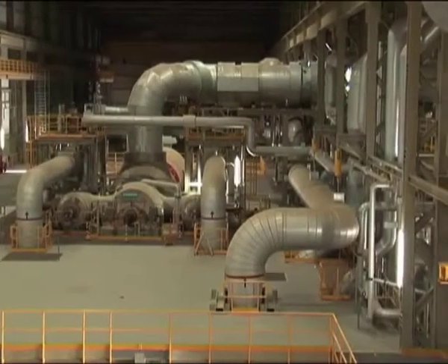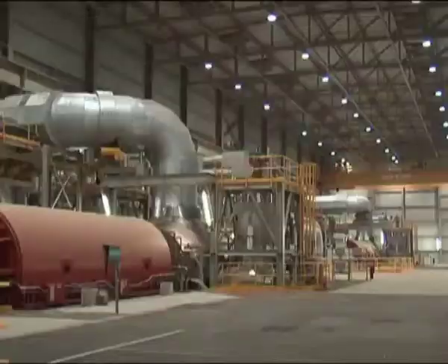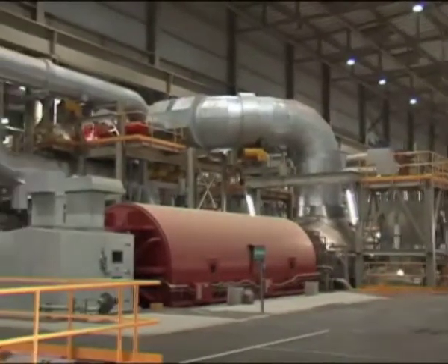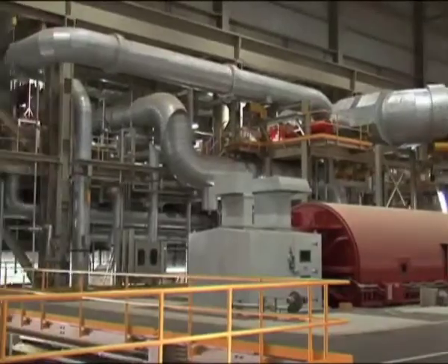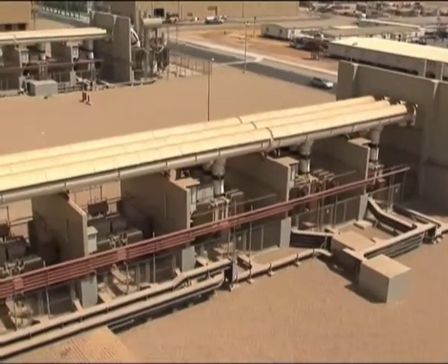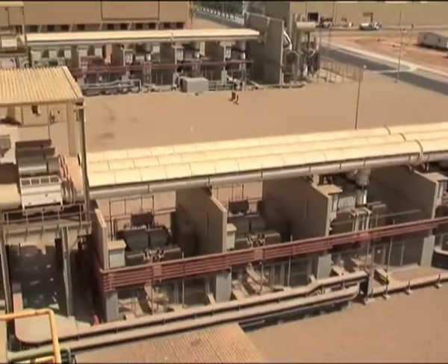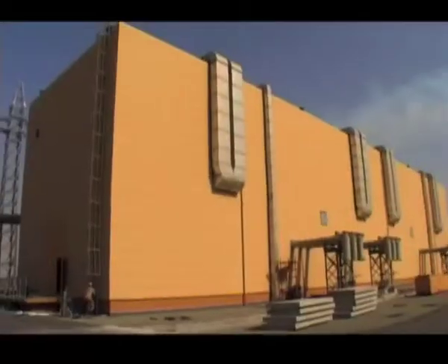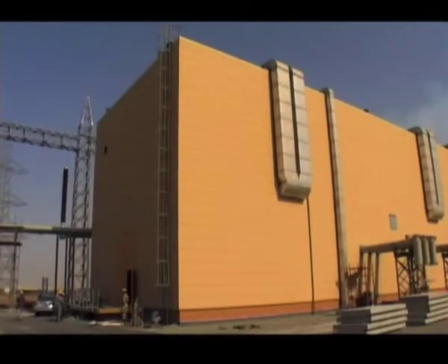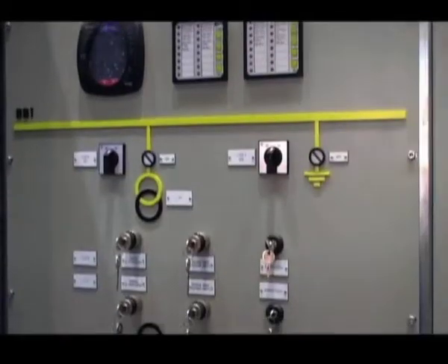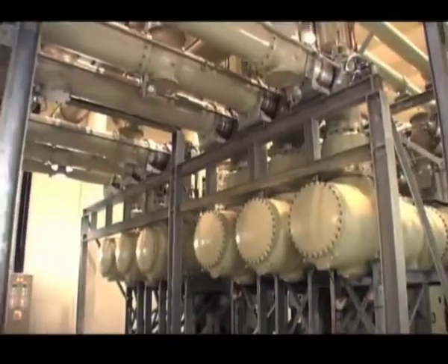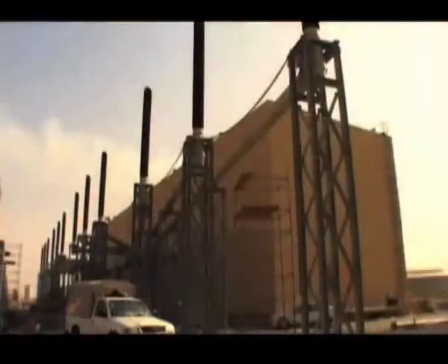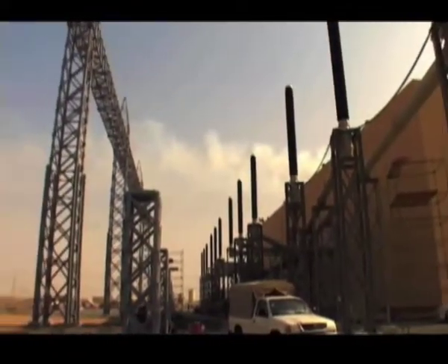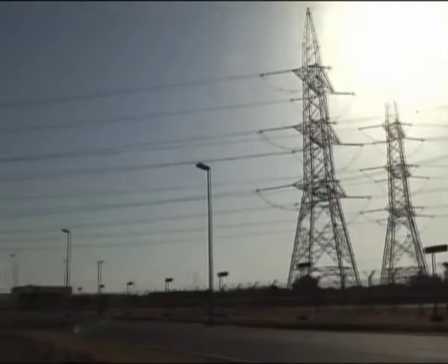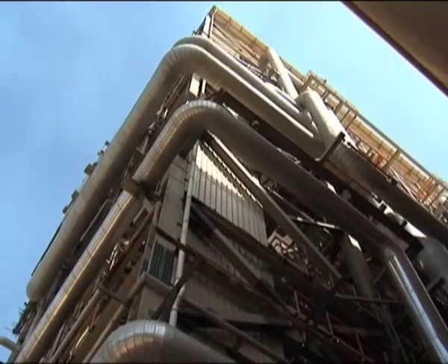Combustion of the crude oil heats a number of pipes containing water, gradually converting the water into steam. The steam from the boilers drives turbines to generate electricity for both plant consumption and also for export to the grid. The link to the grid is provided by the electrical special facility, a 380 kilovolt gas insulated switchgear that connects to the grid through 4 circuits of overhead lines. Exhaust steam is also used for the production of potable water, as it is directed to the multi-stage flash evaporators.